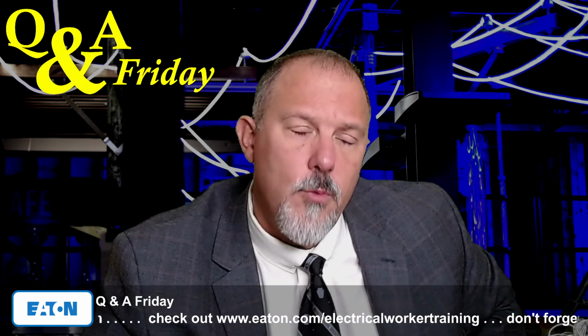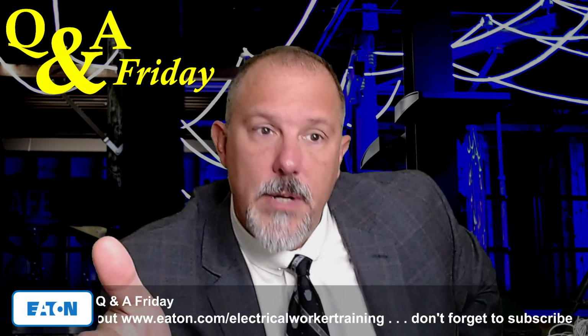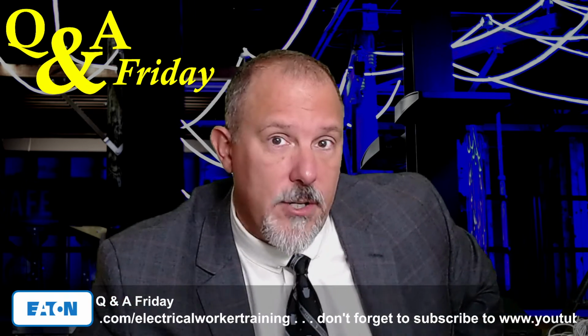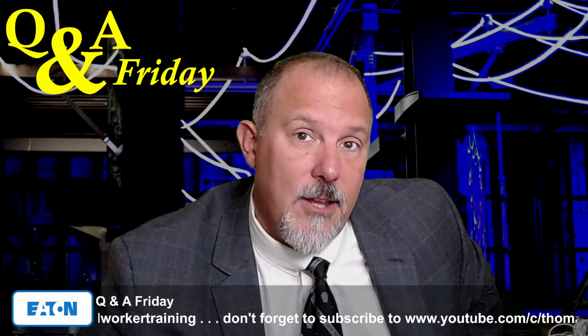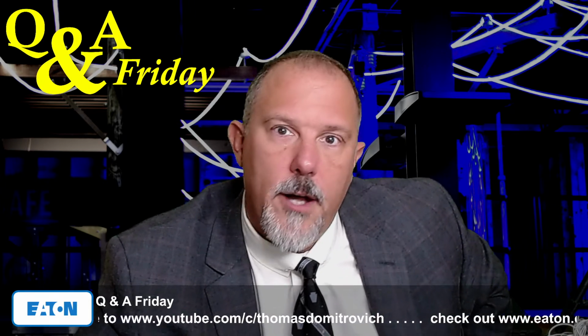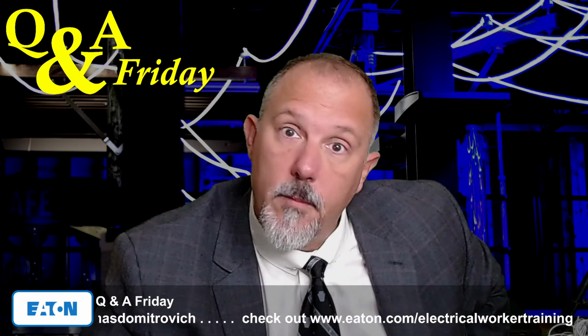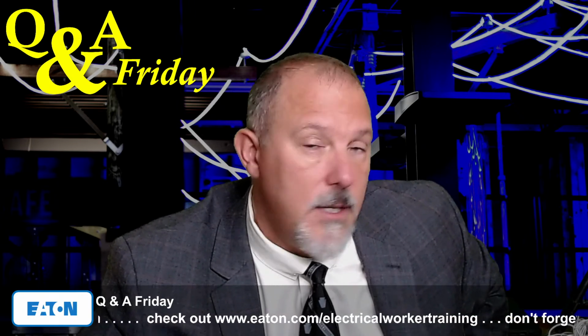So from a NEMA perspective, we put together a document titled Evaluating Fire and Heat Damaged Electrical Equipment to say, when do you need to replace it? When can you refurbish or recondition it? And smoke brings a lot of challenges, just like water intrusion, and there is a water damaged equipment document out there on the NEMA site. Just do a search for NEMA water damaged equipment, and they'll tell you what can and cannot be reconditioned. But whether it be water or smoke, they introduce impurities that can affect the performance of the equipment. Some equipment you can address, and some you can't.